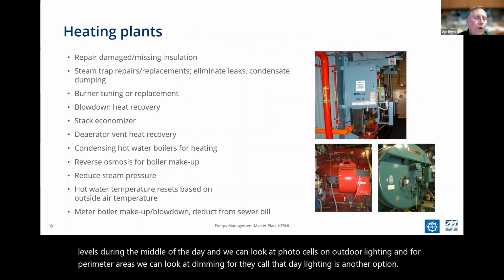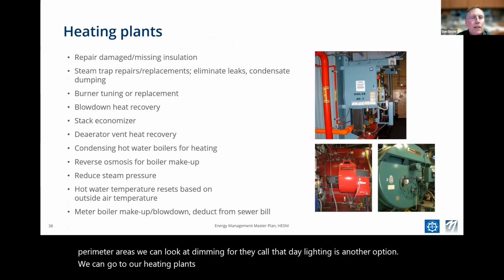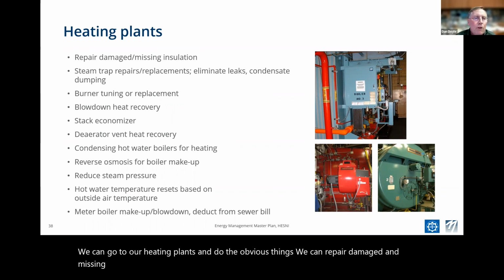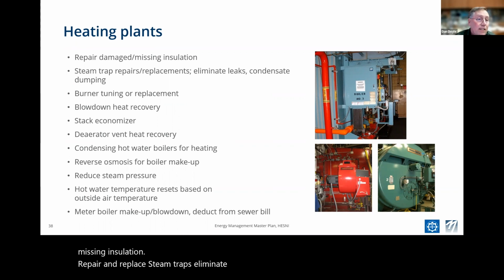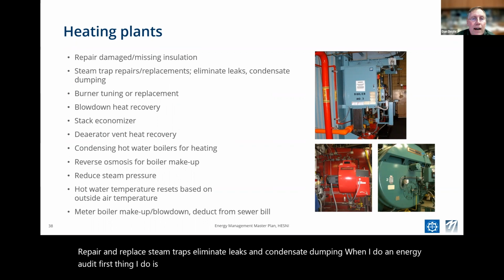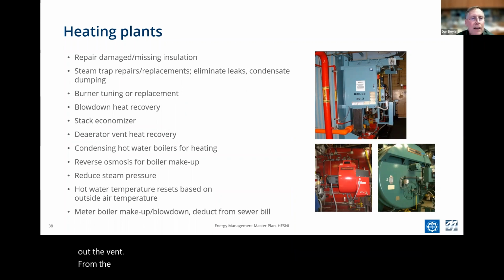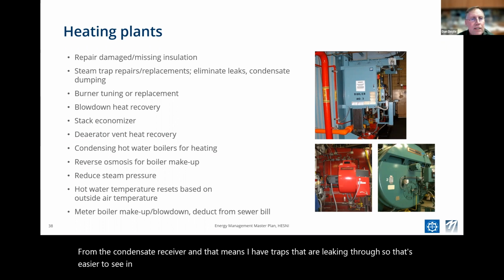We can go to our heating plants and do the obvious things. We can repair damaged and missing insulation, repair and replace steam traps, eliminate leaks and condensate dumping. When I do an energy audit, first thing I do is drive around the perimeter of the hospital and I look for steam coming out the vent from the condensate receiver. And that means I have traps that are leaking through. So that's easier to see in the winter, but generally I drive around the hospital and then I get to a high point on the roof and I look for those steam plumes. You can do the same thing.